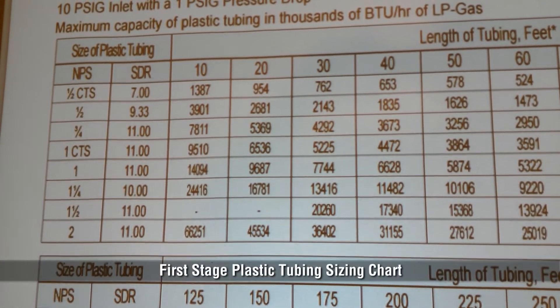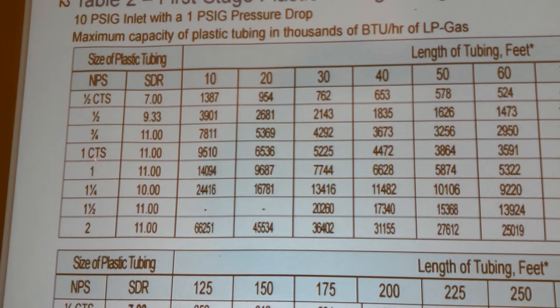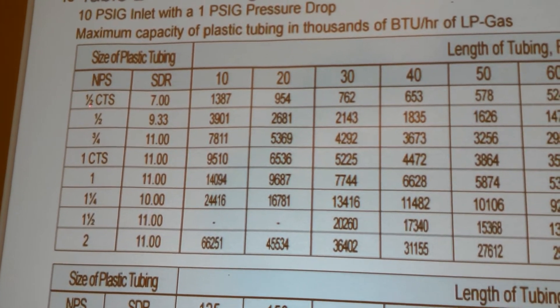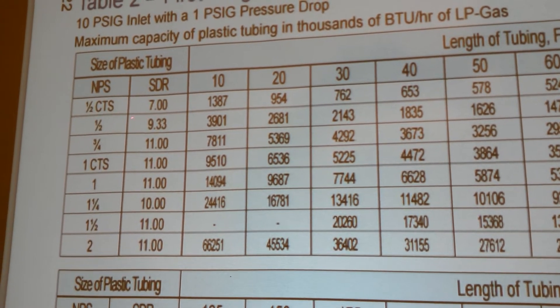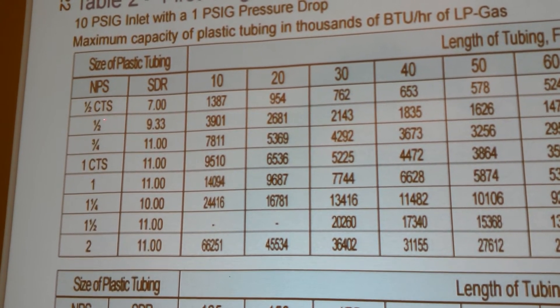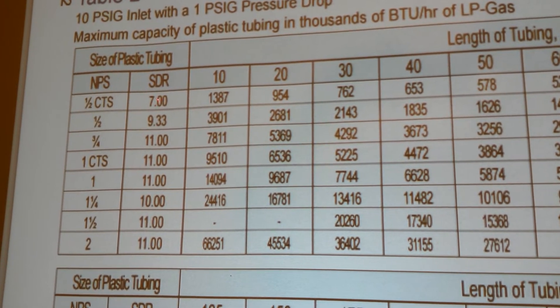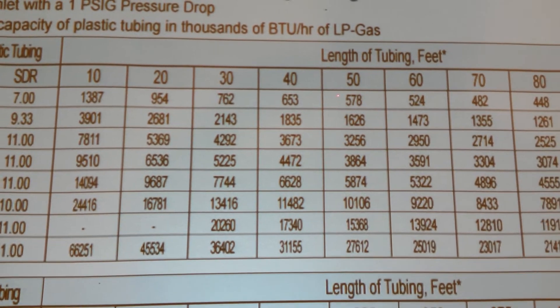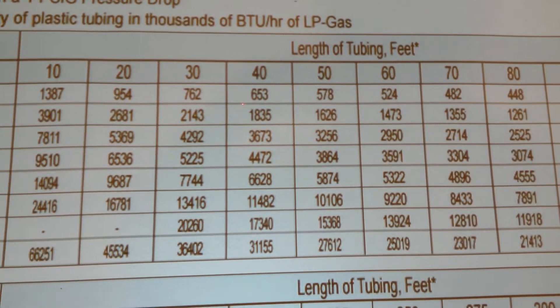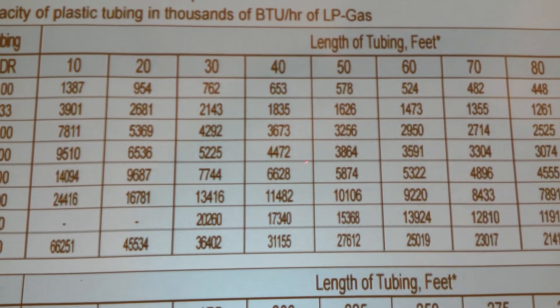Here we're going to be using the first-stage chart to determine what size line we're going to use from our first-stage regulator to our second-stage regulator. For instance, if the tank were 50 feet away from the house and we had a total BTU load of 300,000 BTUs, we could definitely use the half-inch CTS plastic tubing. That'll give us 578,000 BTUs.